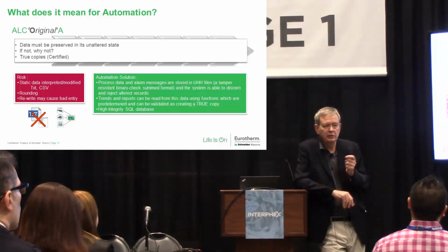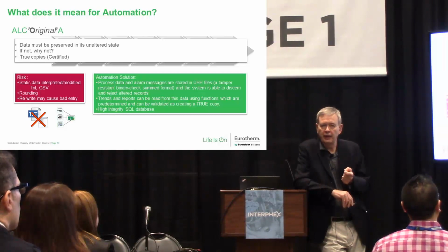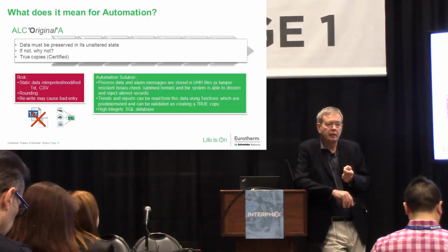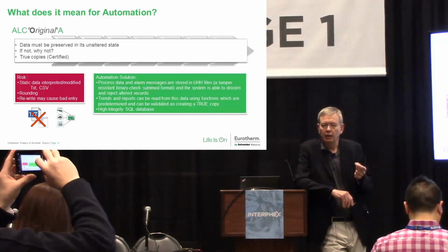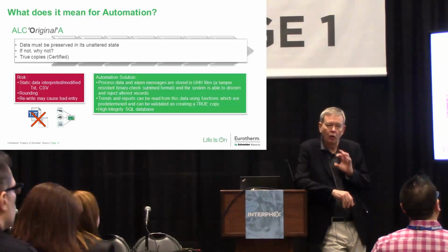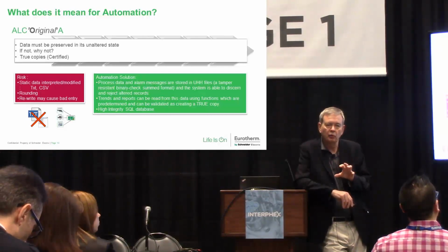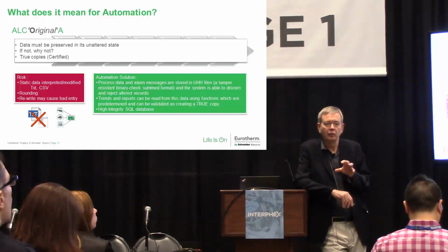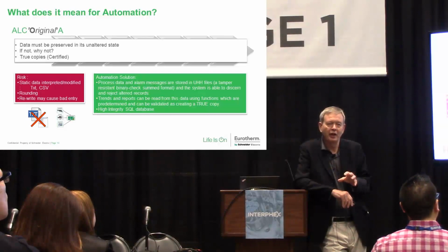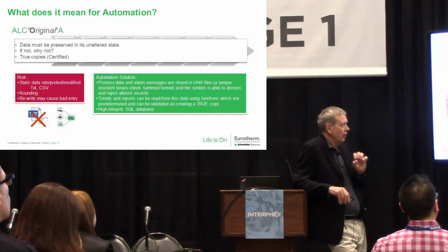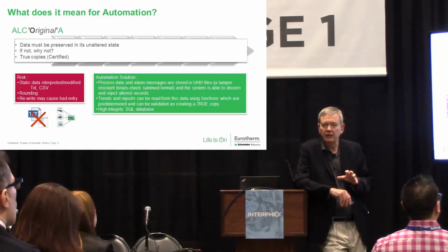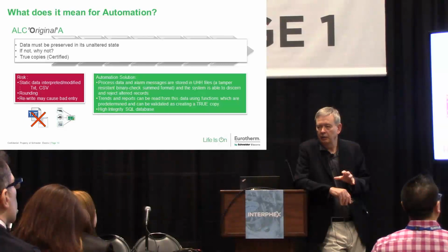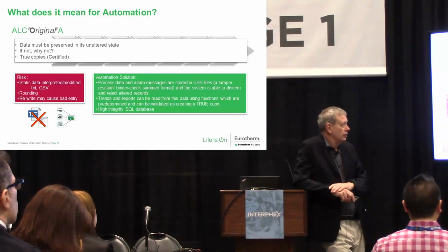Really what you need to have in place is some automation system that records the data but does so in some sort of encrypted way with a binary checksum, so that the original data file is always the original data file. It can never be tampered with. Never say never. We like to call it tamper resistant these days rather than tamper proof. But there are things that you can get out there in the marketplace that will make that data encrypted so nobody can look at it unless they have the right tools. So original data is key, very important.